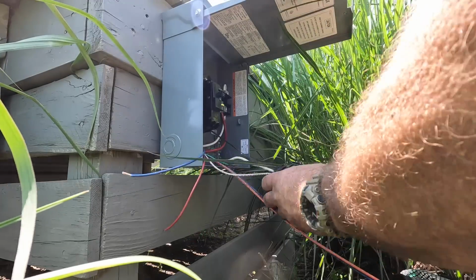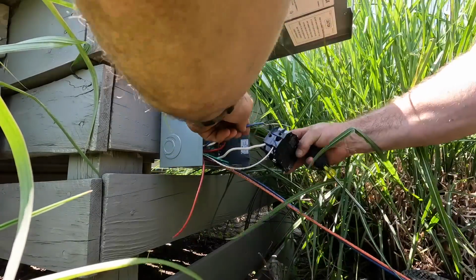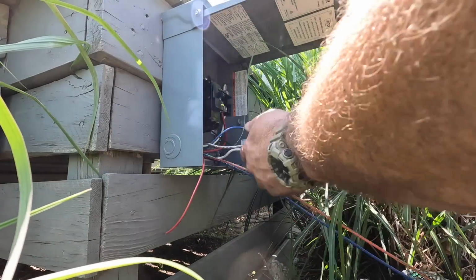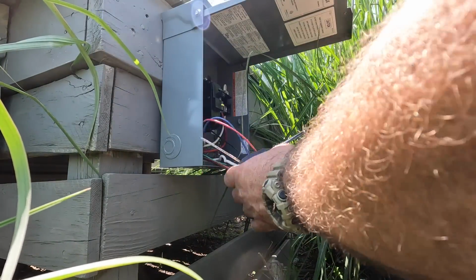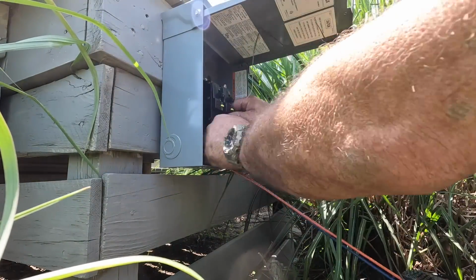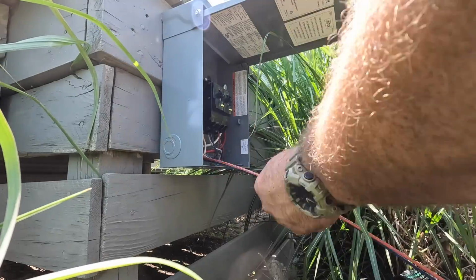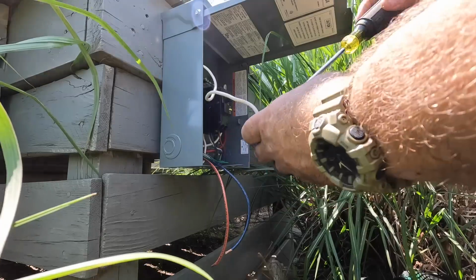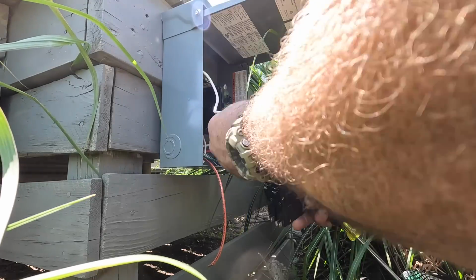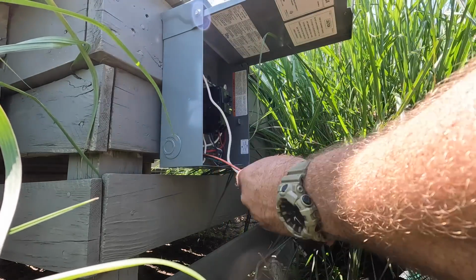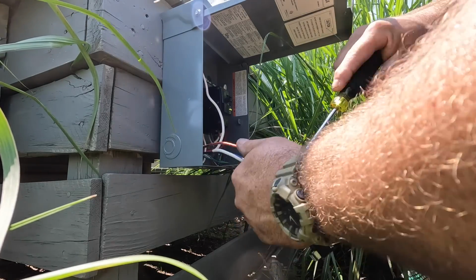So obviously, when I ran my feeder from the panel in the basement, I ran 4 wires. I ran 2 number 6s, which is good for 65 amps. So this is actually on a 60 amp circuit breaker in the supply panel. I ran a number 8 neutral, and I ran a number 10 ground. So a number 10 ground is sufficient for up to a 60 amp circuit.